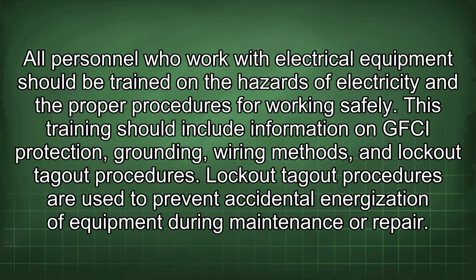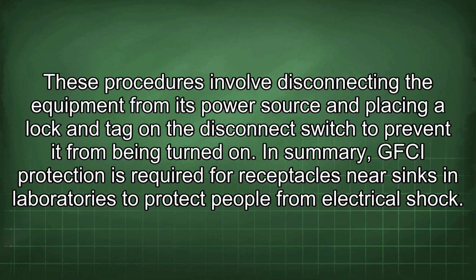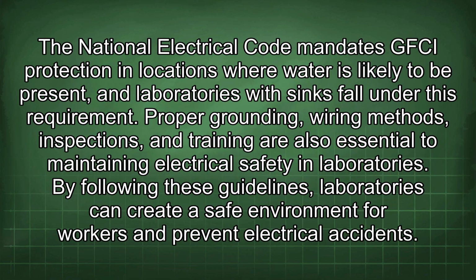Lockout-tagout procedures are used to prevent accidental energization of equipment during maintenance or repair. These procedures involve disconnecting the equipment from its power source and placing a lock and tag on the disconnect switch to prevent it from being turned on. In summary, GFCI protection is required for receptacles near sinks in laboratories to protect people from electrical shock. The National Electrical Code mandates GFCI protection in locations where water is likely to be present, and laboratories with sinks fall under this requirement. Proper grounding, wiring methods, inspections, and training are also essential to maintaining electrical safety in laboratories. By following these guidelines, laboratories can create a safe environment for workers and prevent electrical accidents.